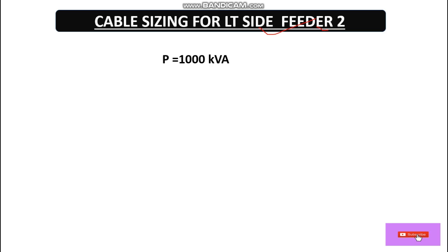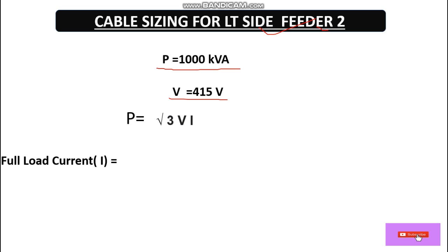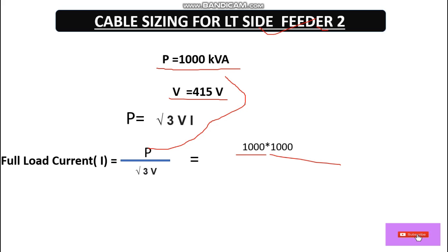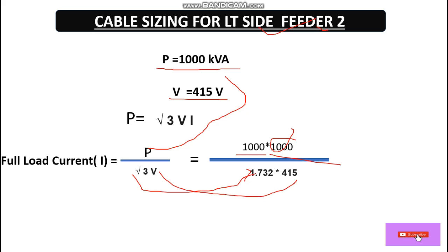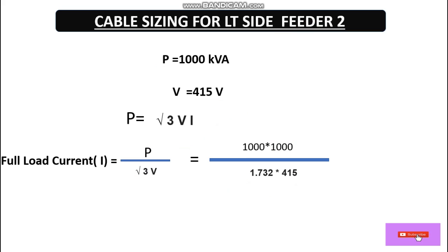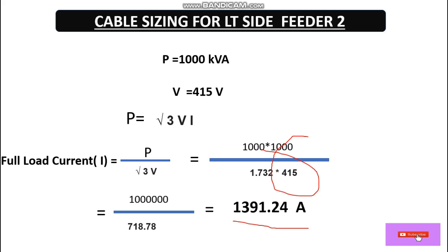Here we are calculating cable size for the LT side feeder two. We have an apparent power of 1000 KVA and voltage of 415 V. The apparent power formula is: S = √3 × V × I. So the full load current I = P / (√3 × V) = 1,000,000 / (1.732 × 415) = 1391.24 ampere. This is the full load current for this feeder.